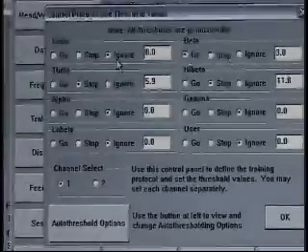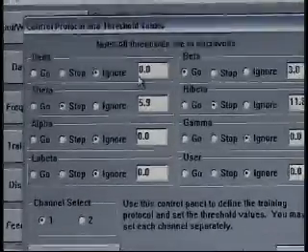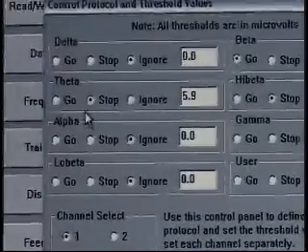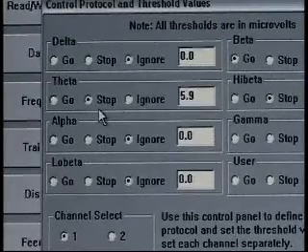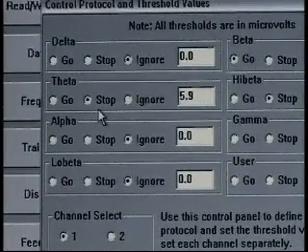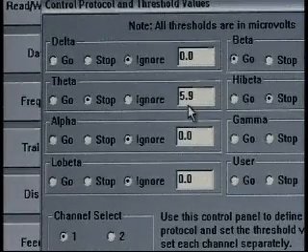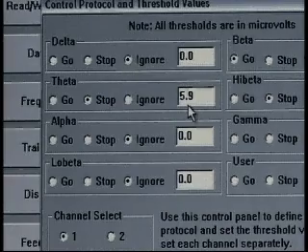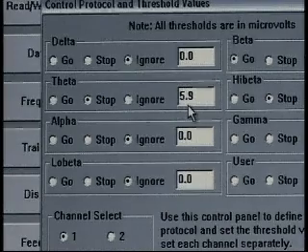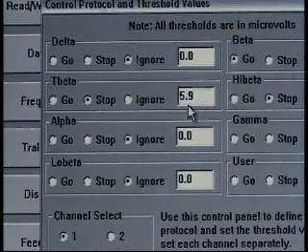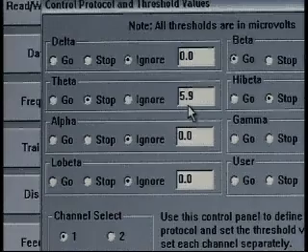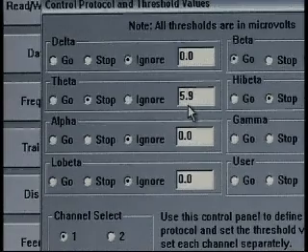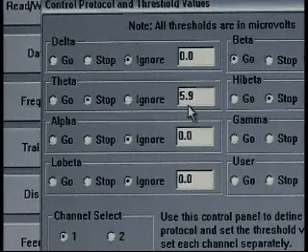As I scroll back up, I can see that my Delta is on ignore. We're not training, we're not going to have any feedback based on Delta today. But theta, for instance, happens to be a stop or an inhibit. We look over and we see 5.9. Oftentimes I'm asked, but isn't theta 4 to 7 Hertz? This actually represents the ending threshold in microvolts.